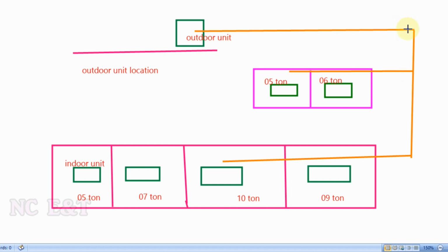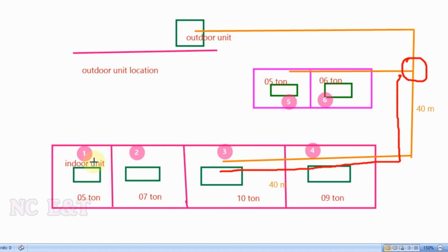There are certain rules that we must follow for the refrigerant piping. One of the rules is that the piping length after the first branch should not exceed 40 meter. Let us consider, in our case for study purposes, that the length from the first branch up to the second unit became 40 meter. So room number 2 and room number 1 we cannot connect with circuit 1, because we have the criterion that after the first branch we cannot go beyond 40 meter of refrigerant piping length.